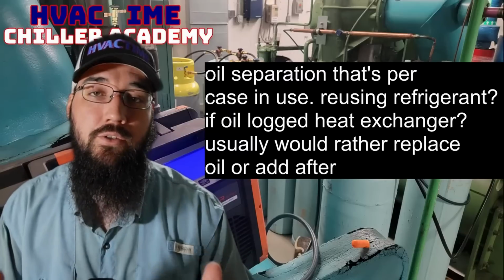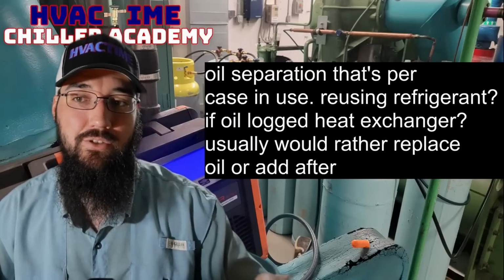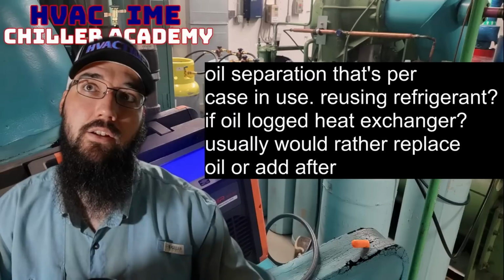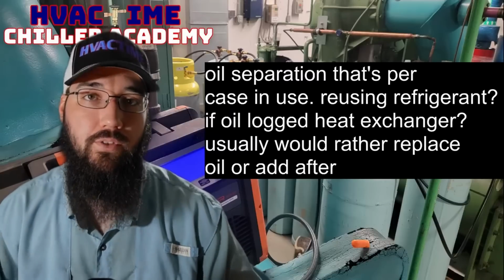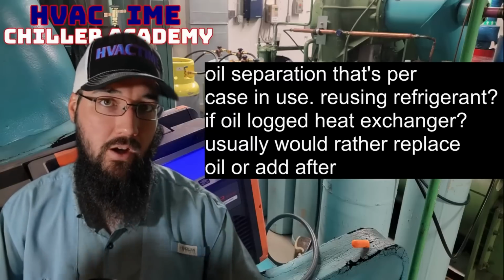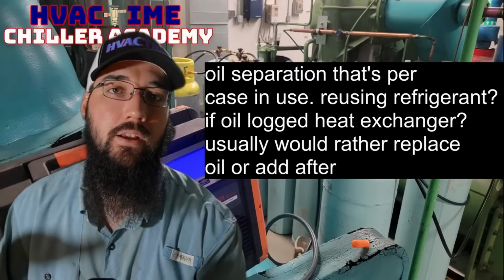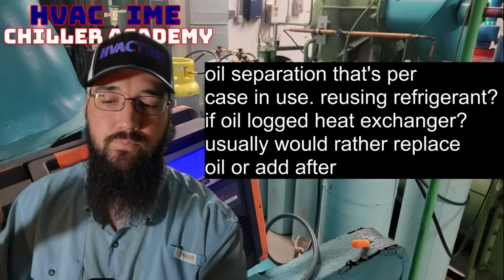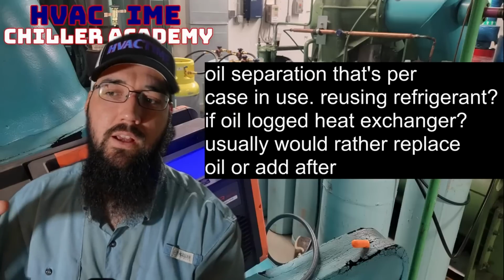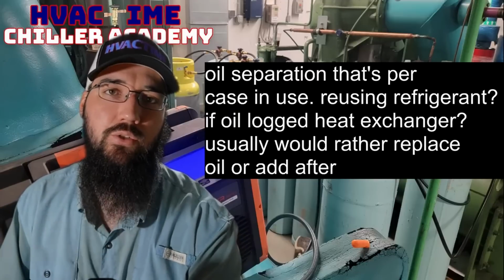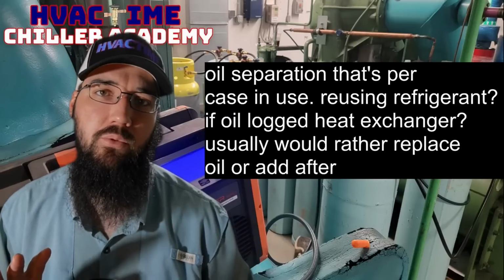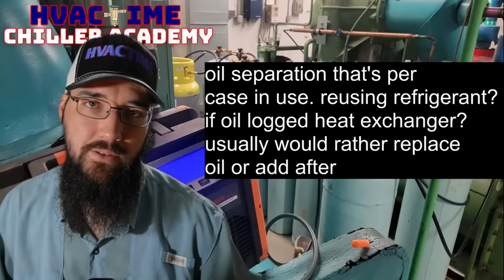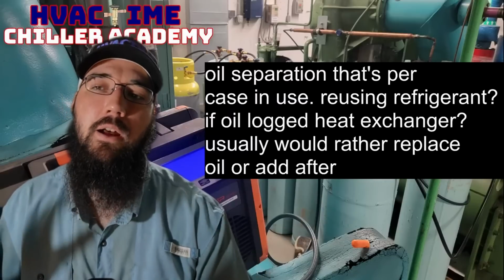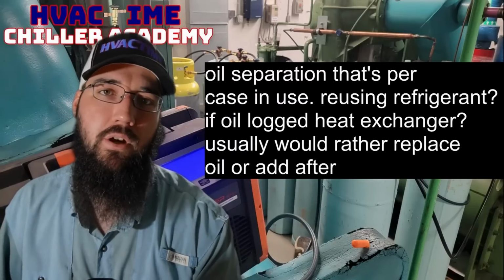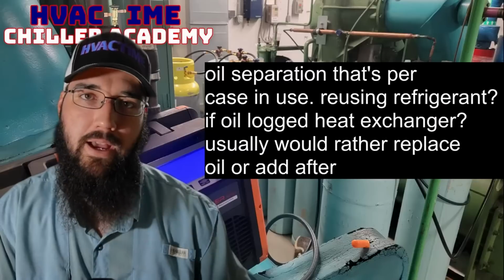Recover the system down, try my best to judge getting the worst of the oil-laden refrigerant, which is going to be on top, into a specific cylinder. From there, I can try to boil that refrigerant back out of that oil and get the refrigerant back.